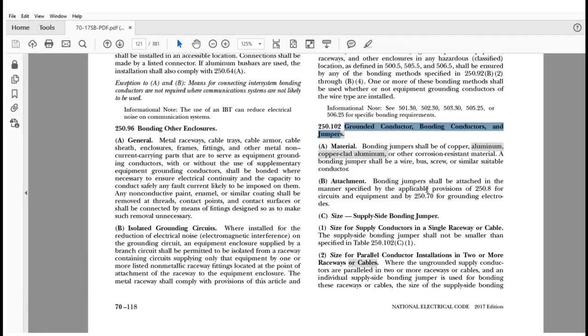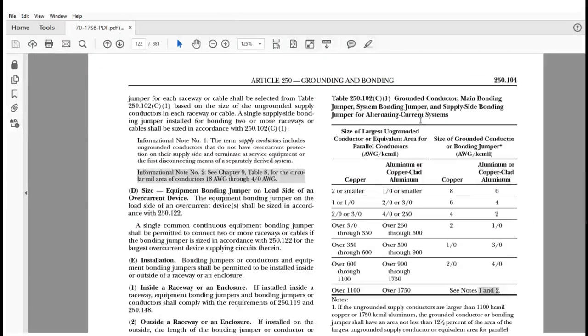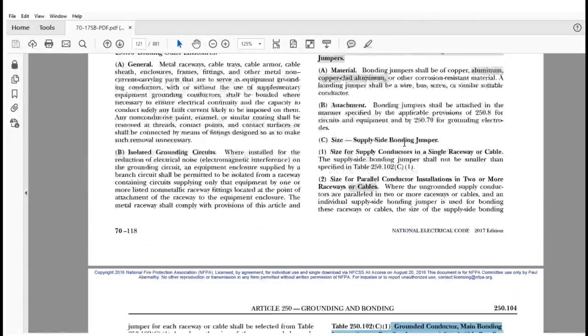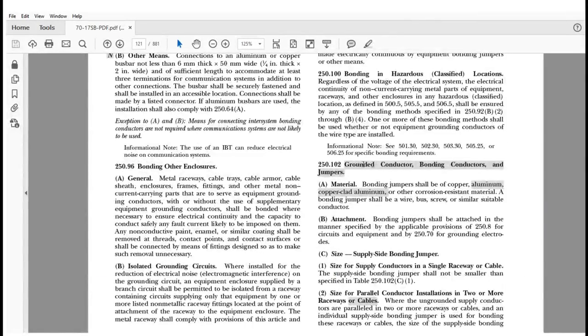Now, in 2014, we have this illustrious table with very good instructions on how to deal with bonding conductors and jumpers and what have you, and grounding conductors. The one big difference in the 2014 is that it didn't say grounded conductor here in the charge statement where the actual code was. It did say it in the table, okay, which was probably just an oversight. It should have been here too. Well, we're always making those corrections. So it did apply, but now it just meets the way it was originated or the way it was intended, I guess.